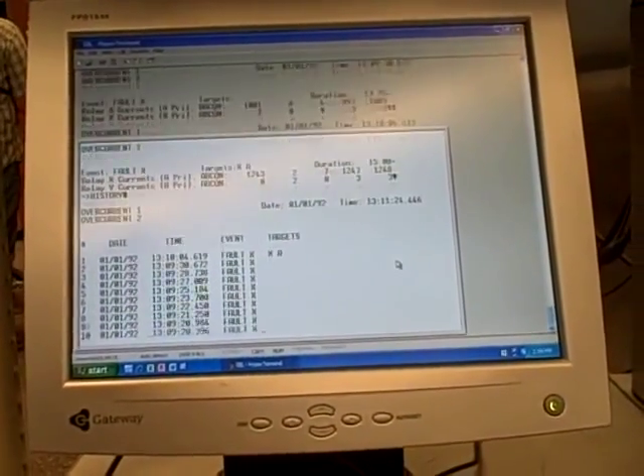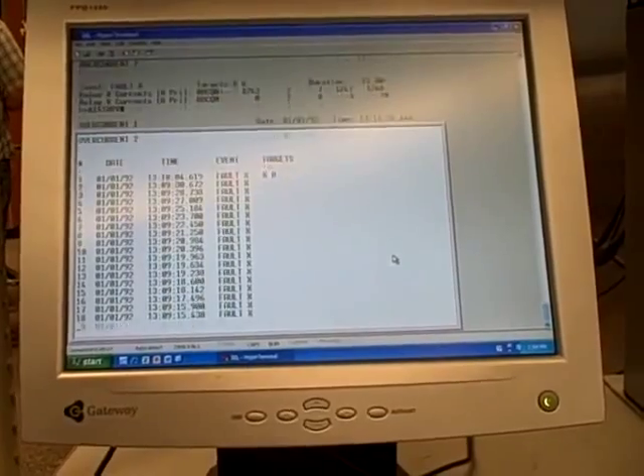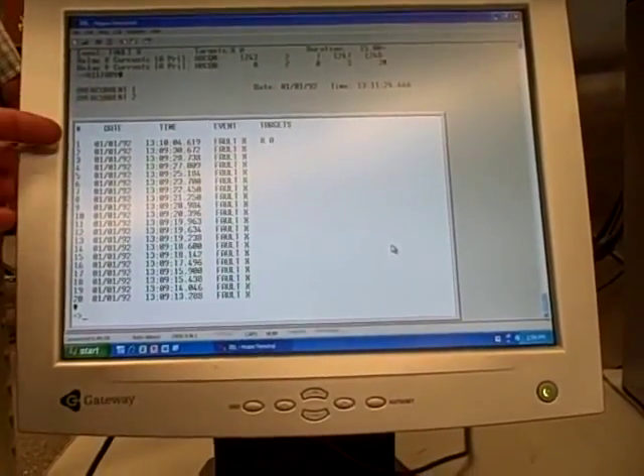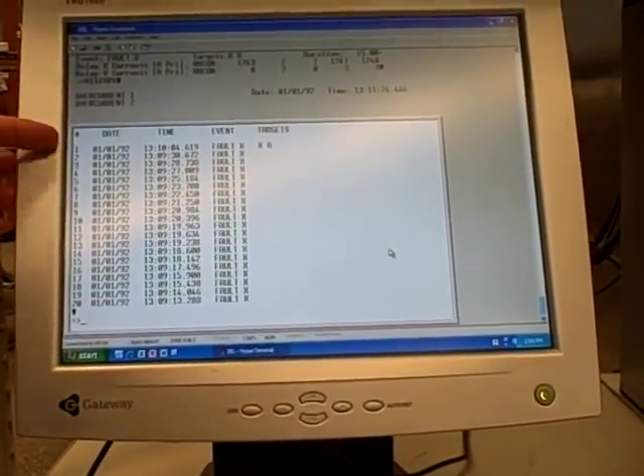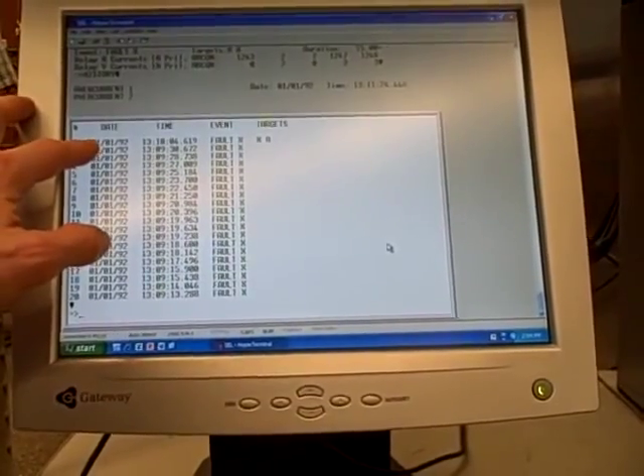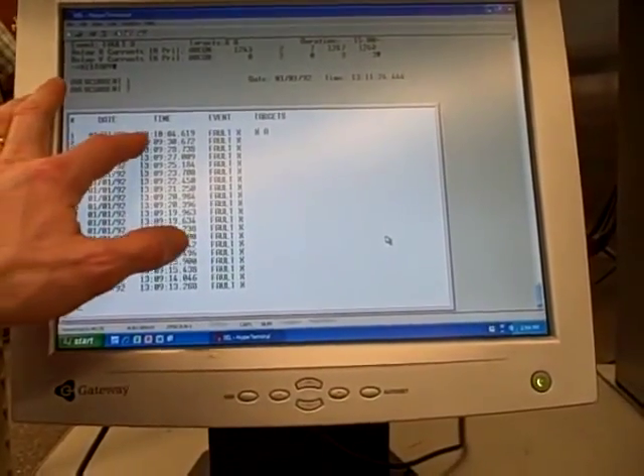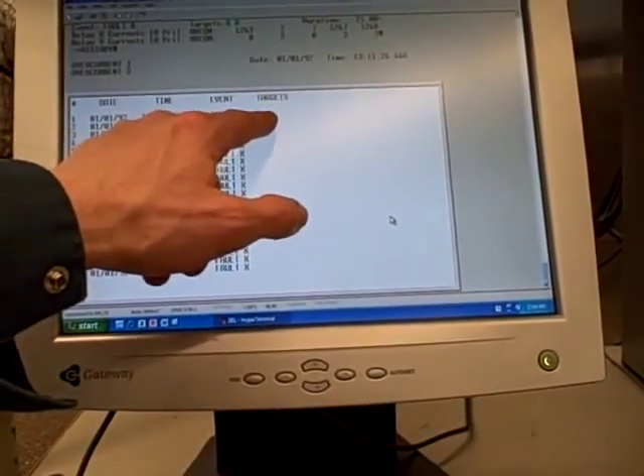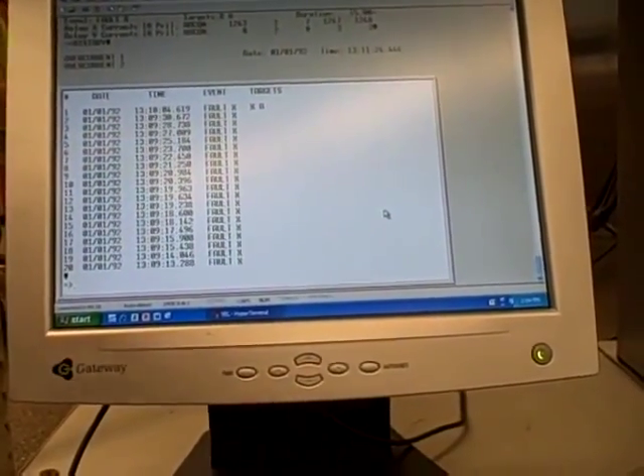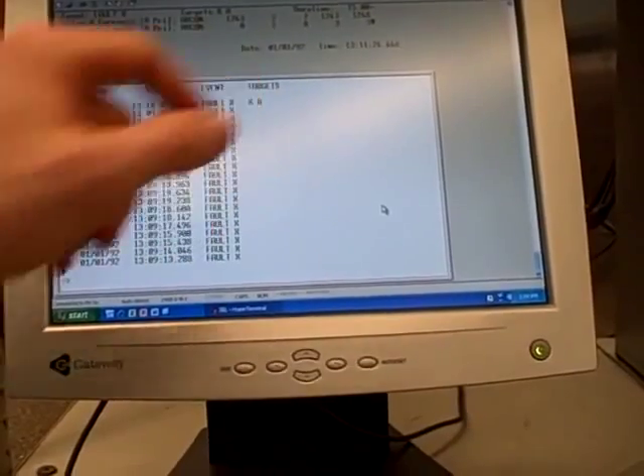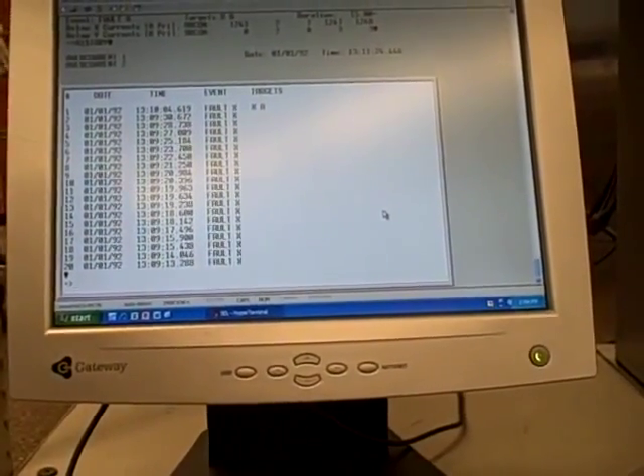I've been testing this relay several times here today and giving it various fault conditions. Our latest event right here, it shows you the date, which is way off. I need to set that. And the time. Here's the fault on relay X, and it shows up as a target. In other words, it actually tripped on A phase for relay X, and that's what tripped out the breaker.